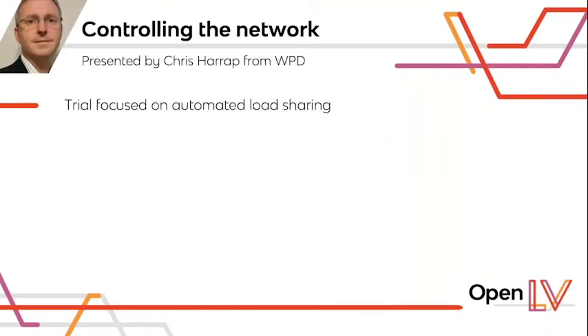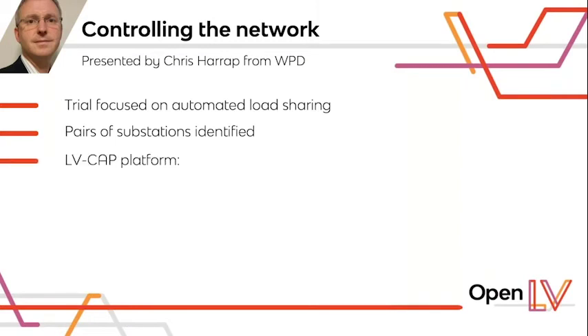The Loadsense network trial aimed to demonstrate the capability of the LV-CAP platform by setting up sites to either mimic or actually undertake automated load sharing. Pairs of connected substations were identified where automated load sharing could reasonably take place. To achieve this, both substations in the pair were fitted with an LV-CAP platform. This equipment then monitored the substation, assessed the capability of the transformer to supply the load, and then optimized the supply arrangement. During periods of low demand, the selected load was supplied by just one substation. During periods of high demand, the load was supplied by both substations.